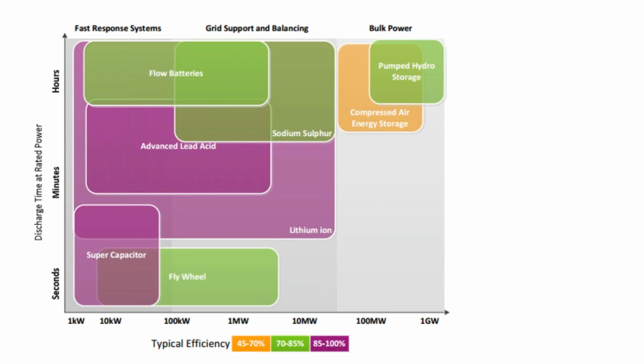And that's where they get into the concept that you need an energy server to tell which batteries to turn on at which times, so that you can combine a wide range of storage technologies on a single job site. In our off-grid class, we talk about how you could have a lead-acid battery providing base load, and then have a lithium-ion battery like the Tesla Powerwall operating in a demand management mode to create a simple energy server, where the lithium-ion battery turns on only when the building demand surges above a certain level, which is hard-coded. We talked about that yesterday, and then whatever is wired in parallel to it with base load, it doesn't really matter.